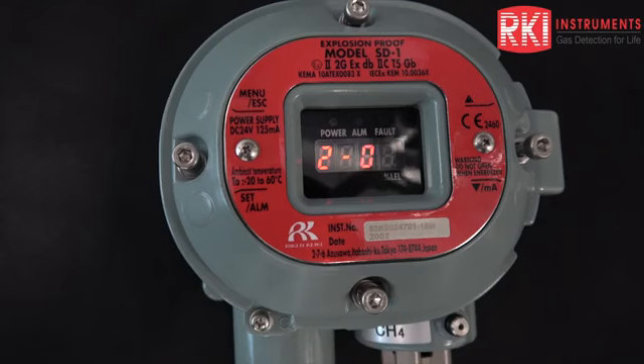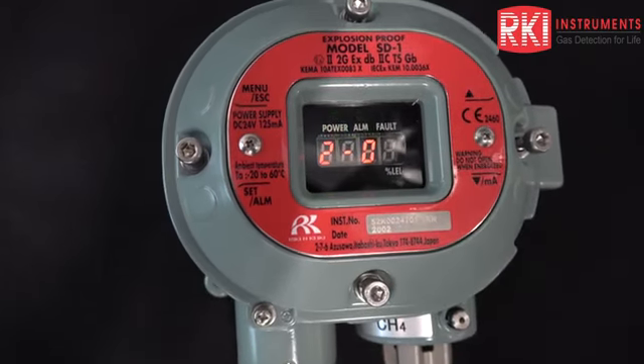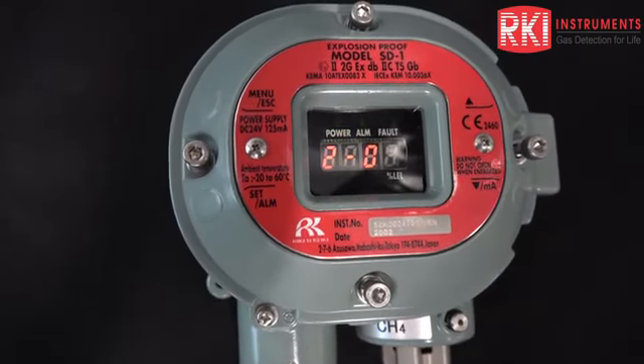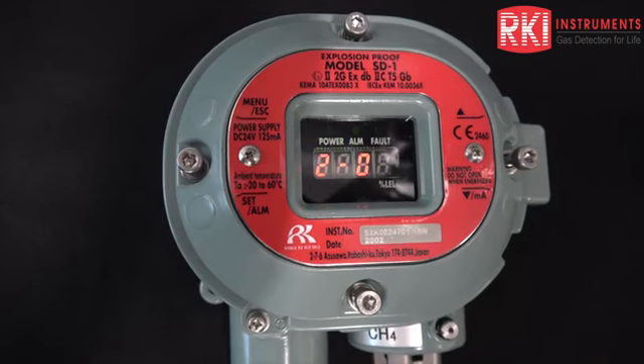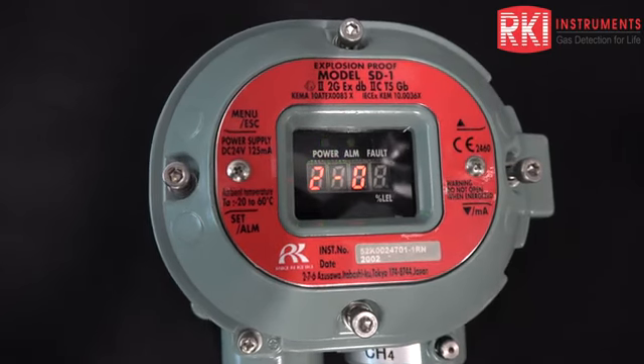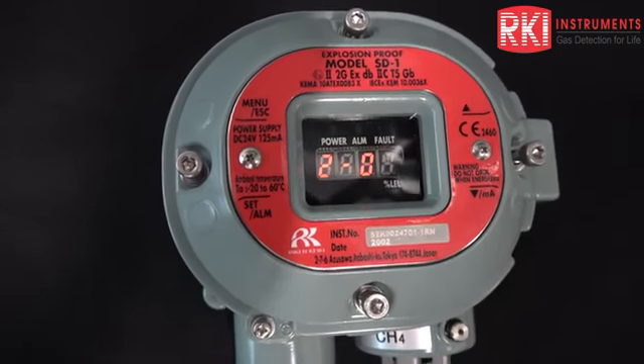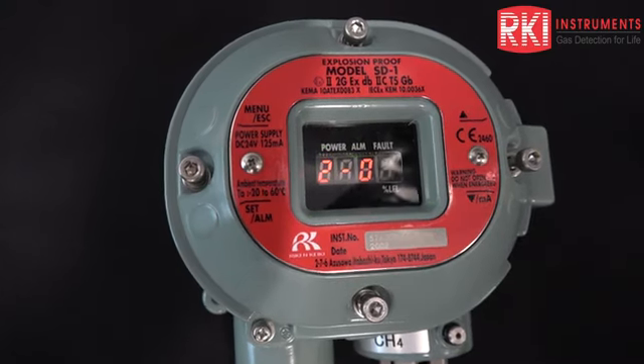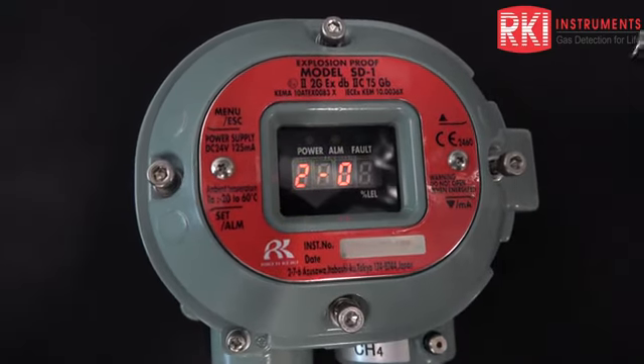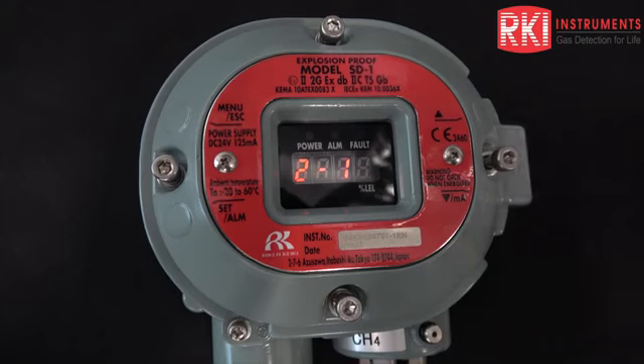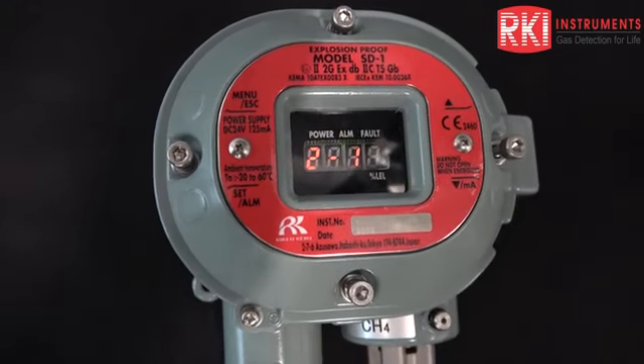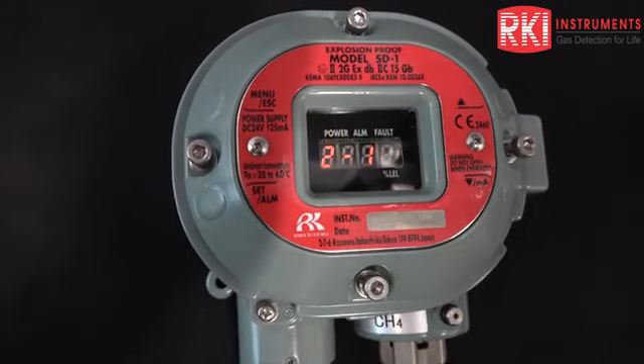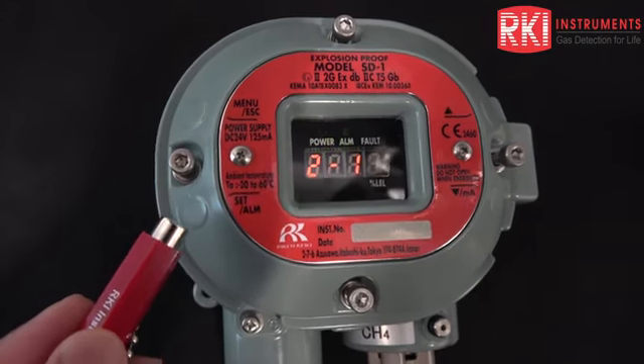And now to do an air adjustment, so zeroing the sensor to ambient air conditions, you want to make sure you're in a gas-free atmosphere, as we are right now in this office. And I'm going to take the display to 2-1. So raise that value up there to 2-1.